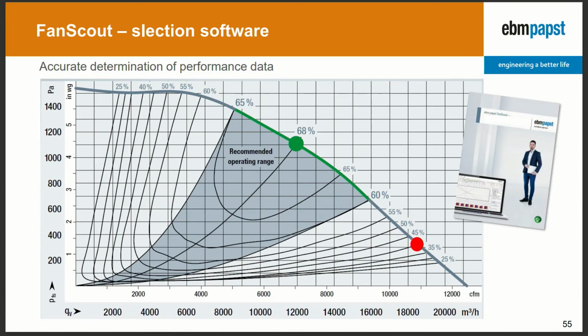So accurate data is something that we can provide, because we measure every fan at maximum speed with the whole setup. So with the original electronic, the original motor, and the original impeller, we measure at maximum speed and 5 other, lower speeds, and with this information we can interpolate. For every duty point we get very accurate information about the power consumption, the noise, the current, and all the other measured data, and we can create graphs like this.